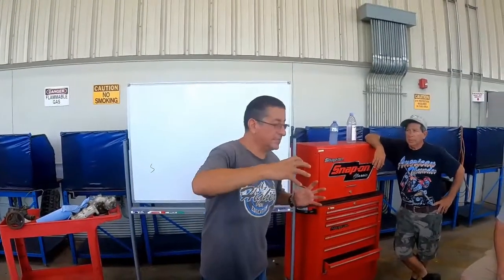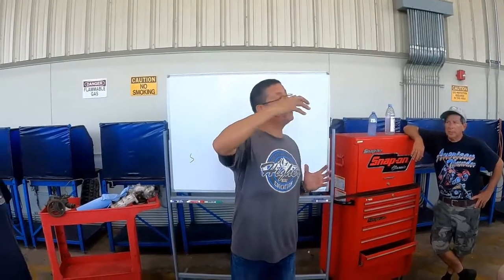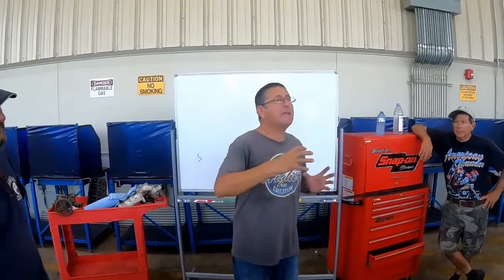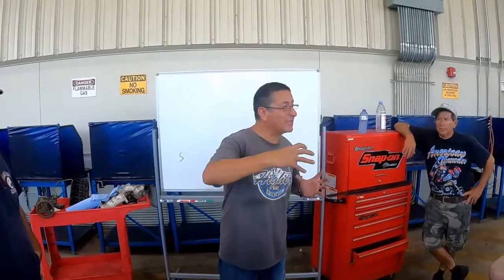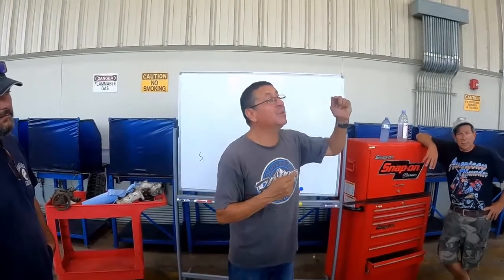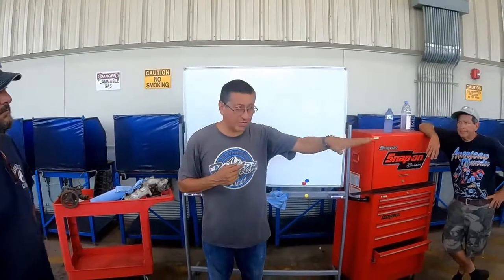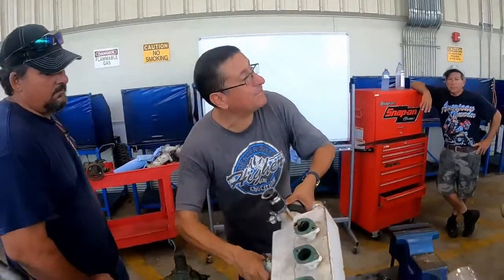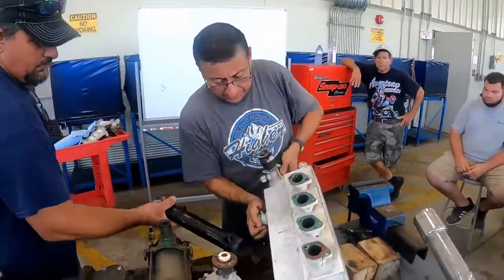If you pressurize the coolant, you can increase the boiling point a little more. Per each PSI that you add in the system, each additional PSI, you increase the boiling point 3 degrees Fahrenheit. The other one is with the elevation. Right now we are going to talk about that.